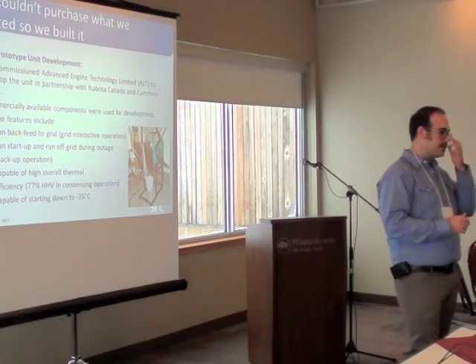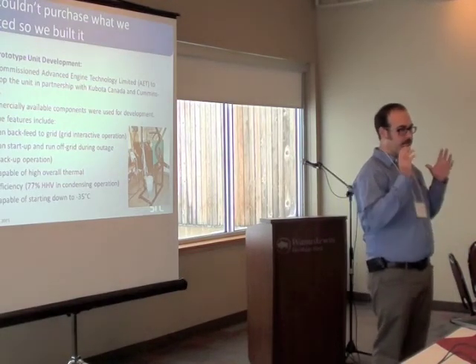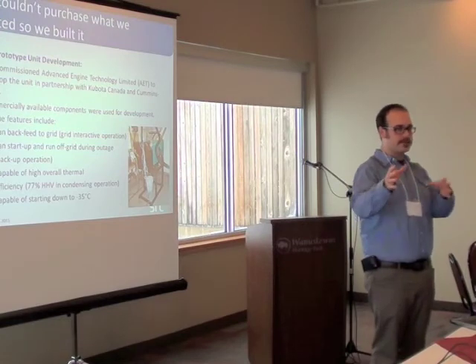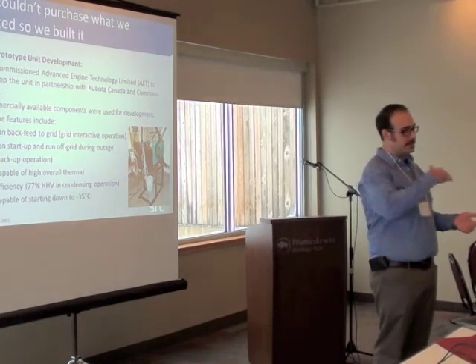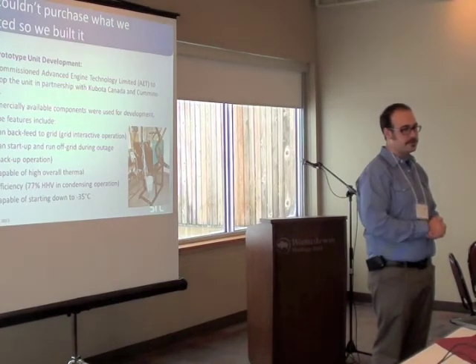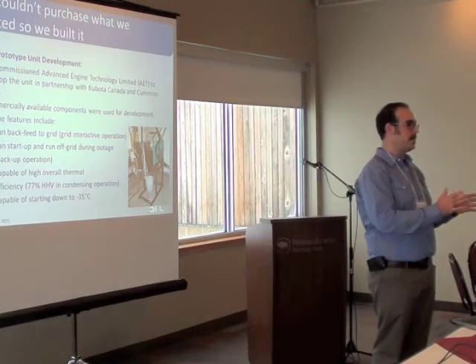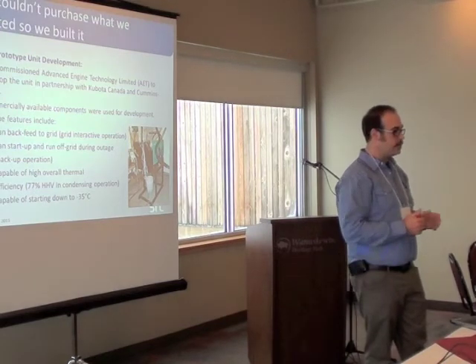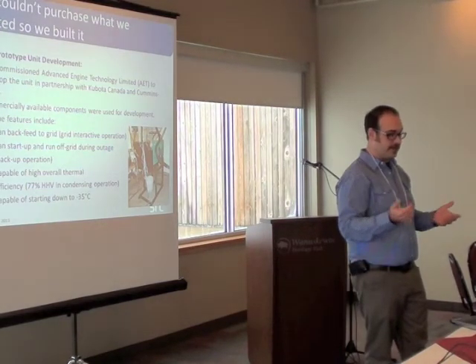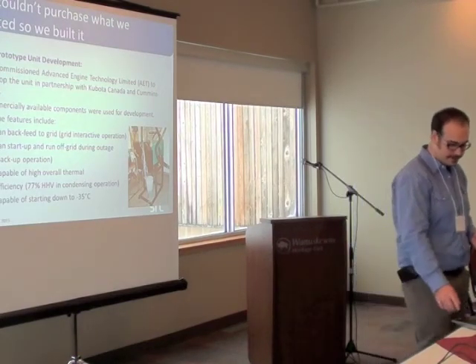What's kind of unique about the system, and it's still unique to this day, is that the system can run in parallel with the grid, so you're using power and exporting power back to SaskPower. Or if the power grid goes out, the system clicks over and supplies power to an essential service panel in the building. So if you had something like a data center that you needed to keep power on, this system would be able to do that. The system is capable of high overall thermal efficiency, considering they developed it in less than a year, and also capable of starting down at minus 35 degrees Celsius, which is important in Saskatchewan.